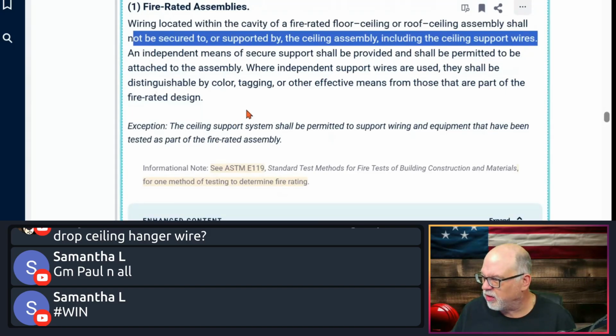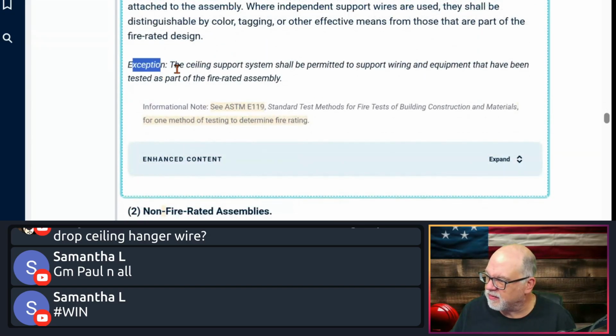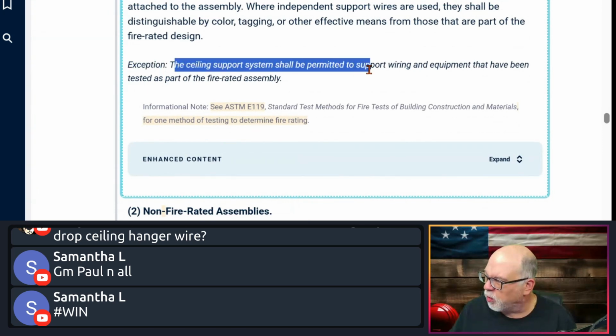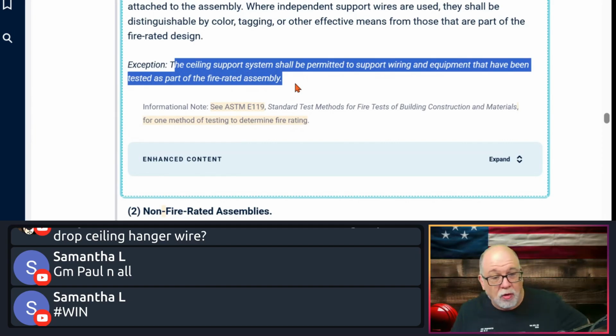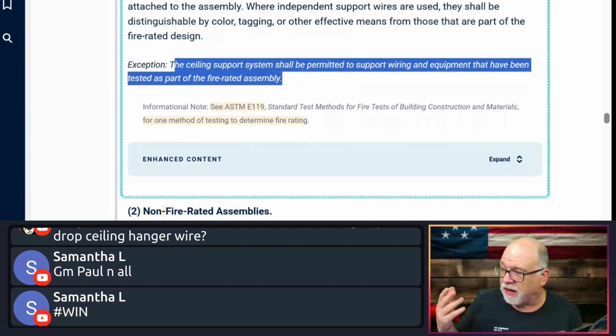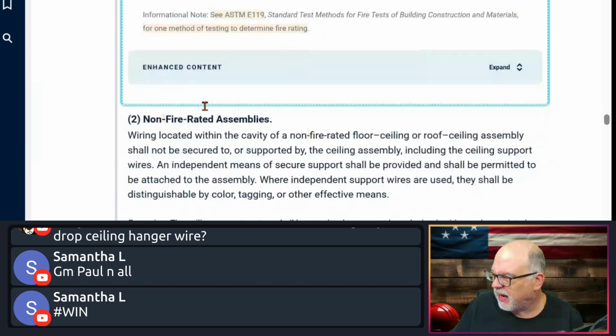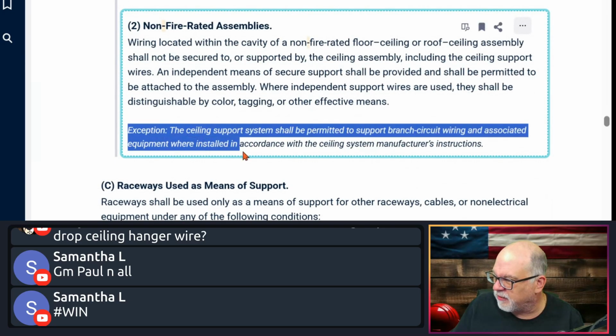Now the only exception to that, there's an exception. It says a ceiling system shall be permitted to support wiring and equipment that have been tested as part of the fire rated assembly. So if you contact the manufacturer and it is a fire rated assembly, for example, and you ask them whether their support wires will not only hold the added weight because the tiles are thicker and have a fire resistive rating, but also support the weight of cables, the manufacturer will tell you whether they evaluated the additional weight or not. And you have the same thing down here for non-fire.